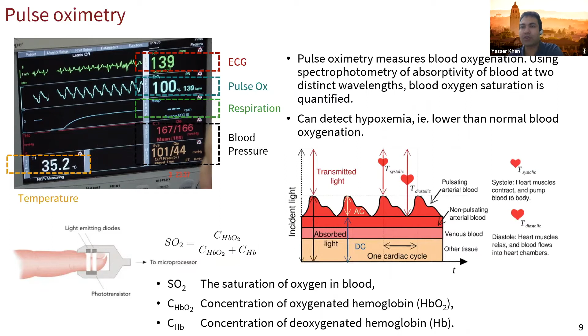Typically you will see this kind of finger clip sensor to measure oxygenation. On one side you have the LEDs and on the other side the photodiode. What we try to do is create a flexible, band-aid-like form factor for this kind of device, so you can wrap it around the finger and it's much more comfortable. We started looking into how we can make a flexible oximeter. The problem is that we are dealing with optoelectronics, which are inherently rigid if you use conventional electronics. But if you go into organic electronics, you can make devices that are thin and flexible. We are using OLEDs, organic light emitting diodes, and also organic photodiodes.